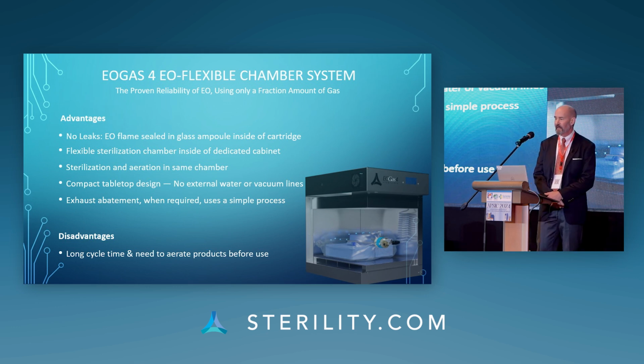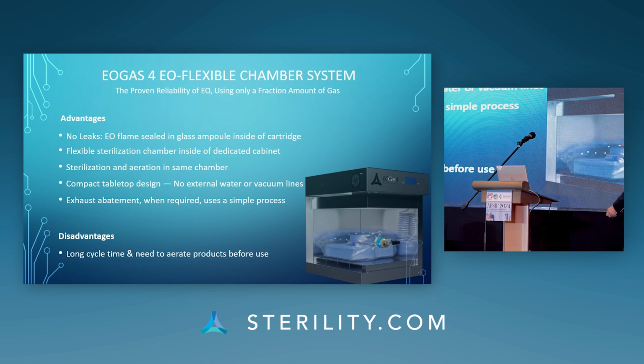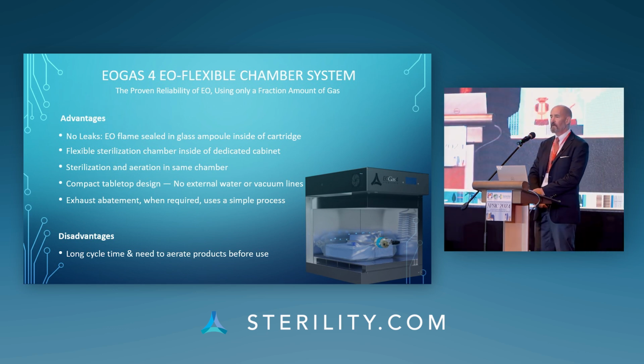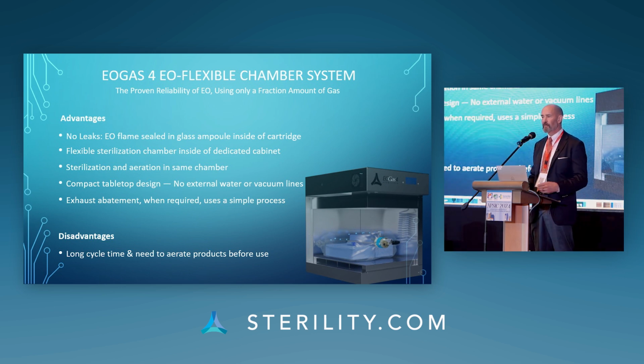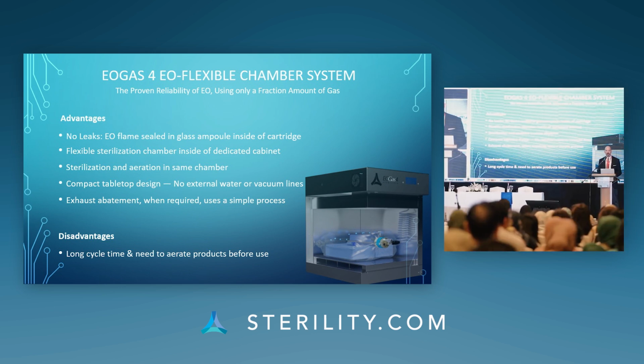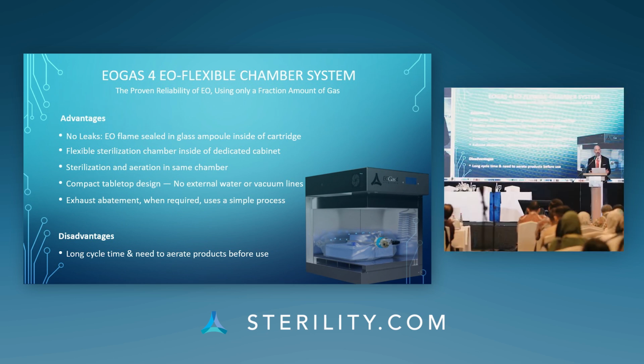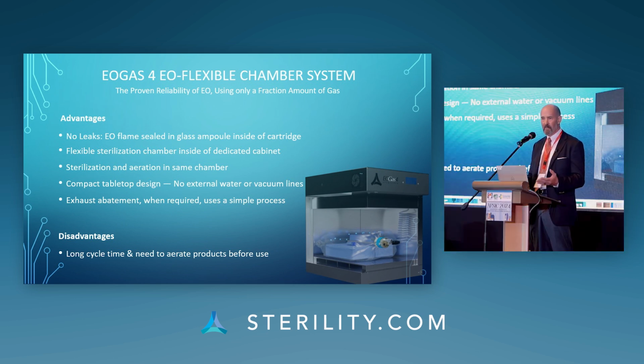What we want to show here is the flexible chamber is a plastic sterilization bag that is inside of a dedicated cabinet. We refer to this as a chamber inside of a chamber. And this is very significant because the sterilizer is this bag, and the sterilizer is inside of its own vent hood. Many ethylene oxide installations have put the ethylene oxide sterilizer in a separate room. We've done this by putting the ethylene oxide sterilizer, the bag, inside of a dedicated negative pressure cabinet so that any leaks are into that cabinet.